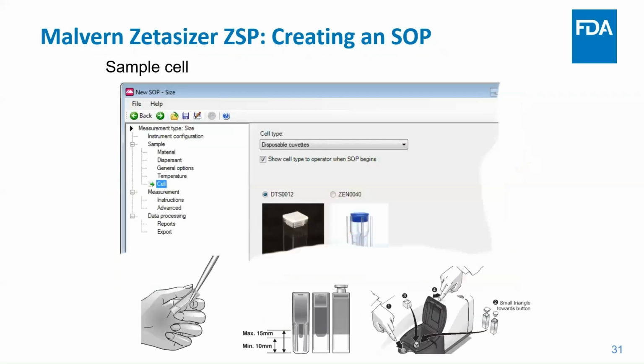So this is another kind of important thing here. You can choose a bunch of different types of cells, disposable ones, whatever, it's fine. But there is a correction inside the software that depends on the cuvette's material properties, because there is a refractive index for when you go through a substance. There's a refractive index change from the air to the cuvette to the liquid inside, and then back out, the light coming back out.